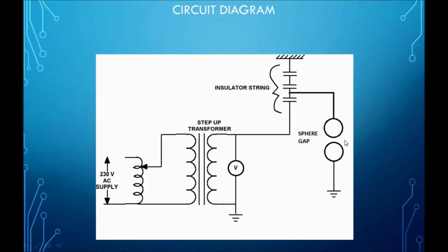Circuit diagram. This is the circuit diagram for measuring string efficiency. You can see this is the auto transformer, with an input of 230 volt AC, and this is the step-up or high voltage transformer. The output can be varied from 0 to 500 kV, and this voltmeter measures the secondary voltage of the transformer. You can see three disc insulators connected in a string. This is the first insulator, this is the second insulator, and this is the third insulator.